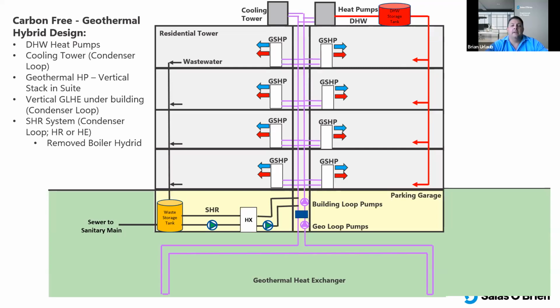The heat pump technology on the domestic hot water side has really gotten better. The efficiencies are there, so you can electrify a building now without impacting the total peak KW, which is really important when we get into some of these very large buildings, which I'll show you. Certain rate structures from utilities will have major implications if you get over a threshold on your peak - then they get charged a different rate, which can be very high.